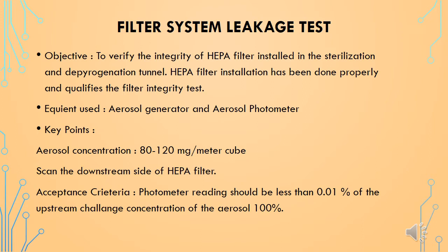Now we will see the second qualification test: filter system leakage test. The objective of this test is to verify the integrity of the HEPA filter installed in the sterilization and depyrogenation tunnel, to confirm that HEPA filter installation has been done properly and qualifies the filter integrity test. The equipment used are an aerosol generator and aerosol photometer.